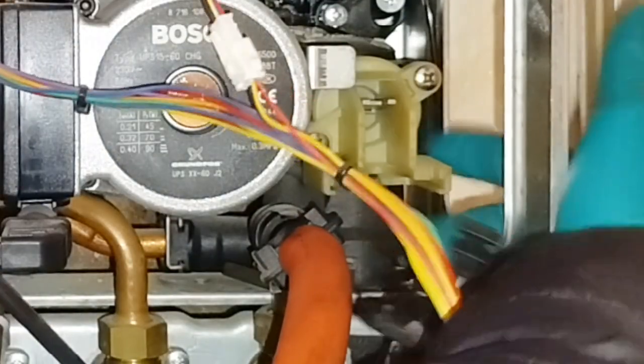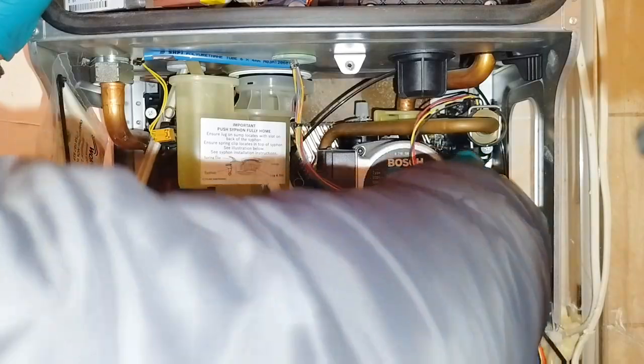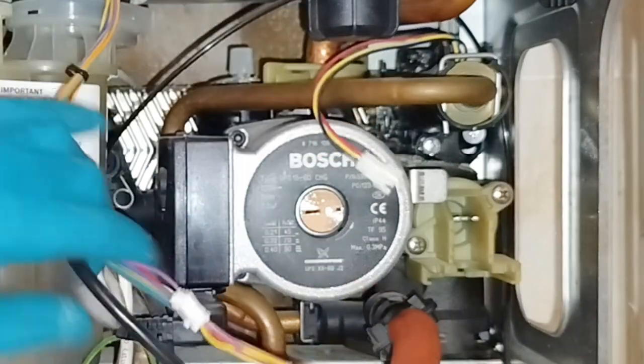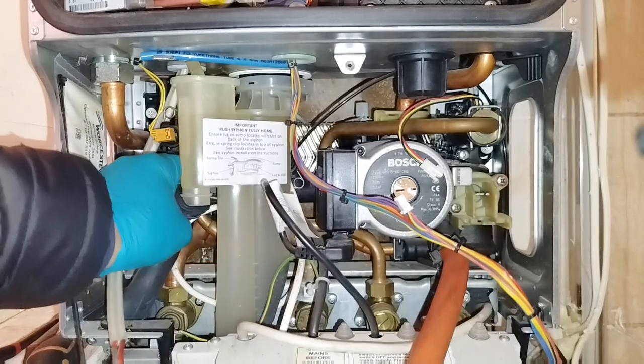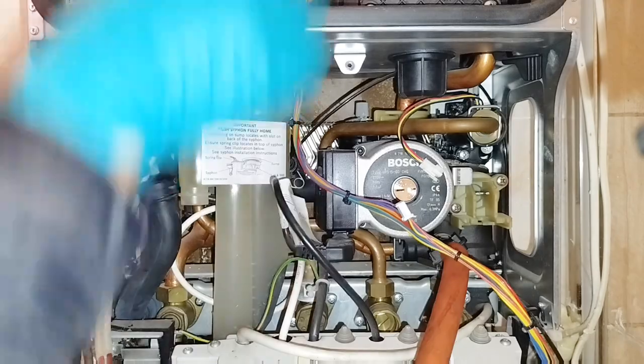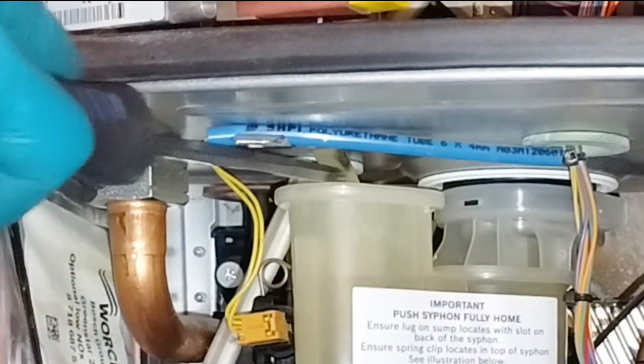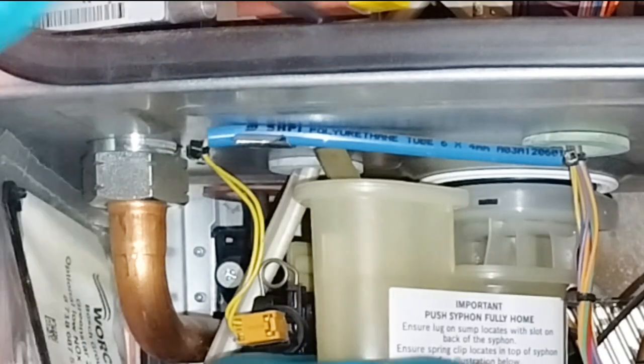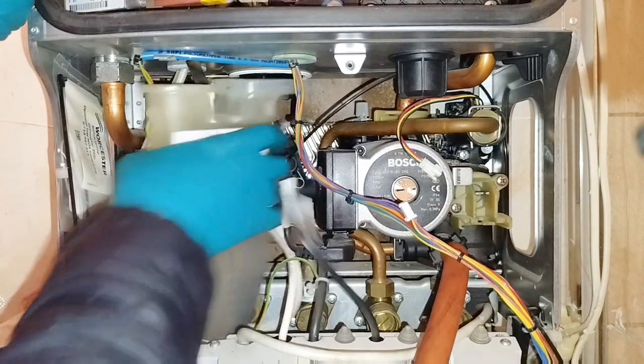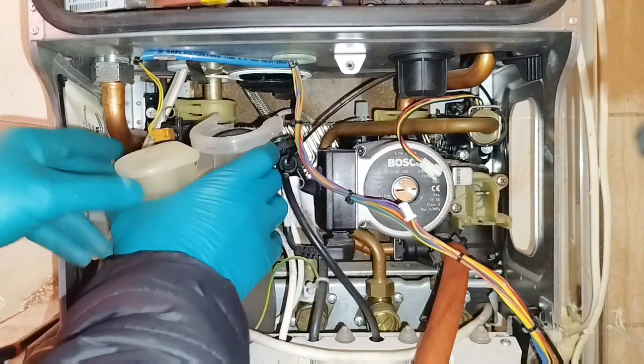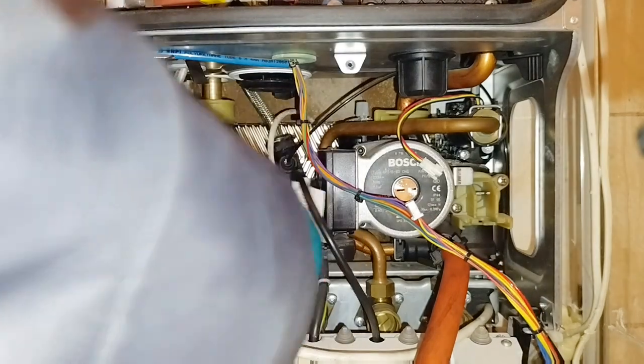And I've removed the diverter valve motor to allow it to come to the middle. It's always a good idea to push this paddle manually downwards, because it can sometimes, with the pressure of water, stick upwards and not allow the water to come out. Then we've removed the flow turbine's cable. After that, we've removed the hose from the condensate trap. This little clip holds the trap in position, so lift it up and then pull the trap out. So we've just pushed the trap downwards. There was space between the pipes, we've pushed it down and taken it out.